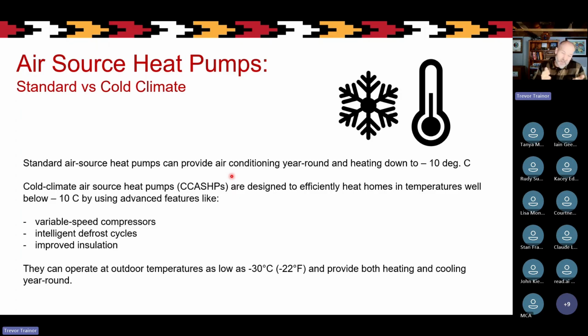There's two types generally of air source heat pumps. There's the standard air source heat pump, which has been around a lot longer. A standard air source heat pump can provide air conditioning year round and can provide heating down to about minus 10 degrees Celsius. So relatively limited to where these can be used in Canada because of that limitation. After minus 10, typically they aren't able to provide any heating energy and a backup source is needed.